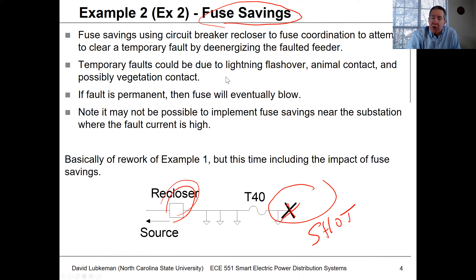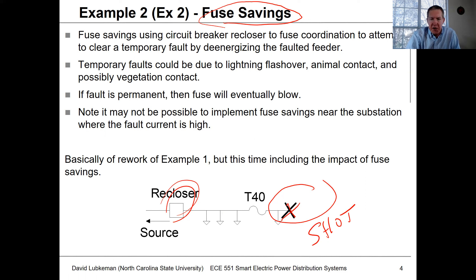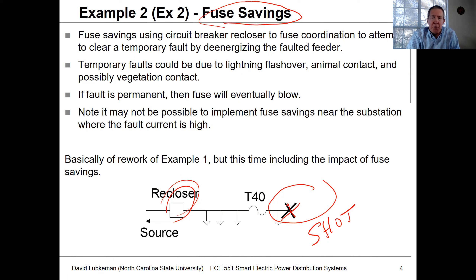Just because you have an upstream breaker and a fuse doesn't mean fuse savings is activated. You have to have the right fuse in place and the logic and recloser set up correctly. That's why in the previous example, we had a situation with no fuse savings where the fuse would blow for any type of fault. Now we'll look at what happens when fuse savings is set up.